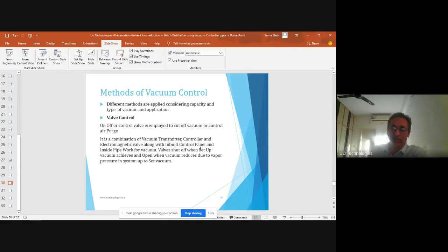How will you control the heater? You give power, current, to the heater. Depending on the temperature, you control the temperature by controlling the power supply to the heater. In this, it is a combination of a vacuum transmitter control and an electromagnetic valve, that is, an on-off valve, with a complete panel and inside pipe work for vacuum. The valve closes when the set vacuum is reached and opens when vacuum reduces due to the vapor pressure in the system. So this is the valve control.